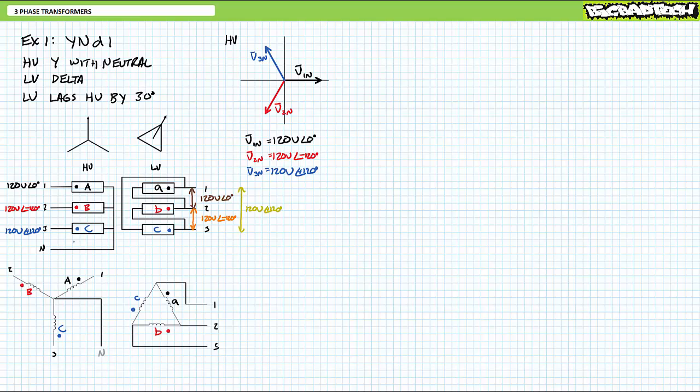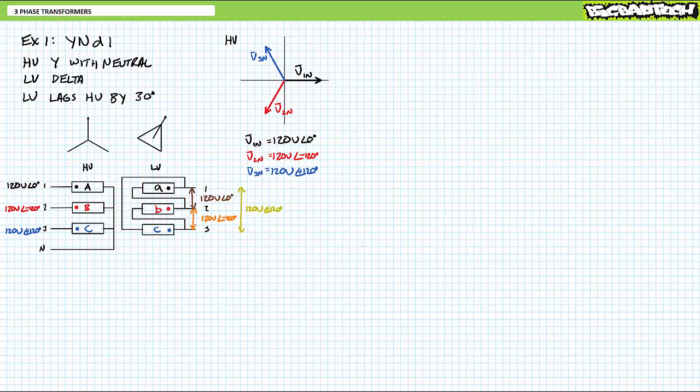Note the dramatic overemphasis of the term line-to-line. A YND1 configured transformer is effectively taking the line-to-neutral values of the high voltage Y and making them the line-to-line voltages of the low voltage delta. For the Y-configured high voltage side, each winding experiences the comparatively smaller line-to-neutral voltage of 120 volts with a respective phase shift of 120 degrees between each phase. Those with an understanding of three-phase AC and phasor math will immediately spot why the 30-degree phase shift occurs between the Y-configured high voltage side and the delta-configured low voltage side.